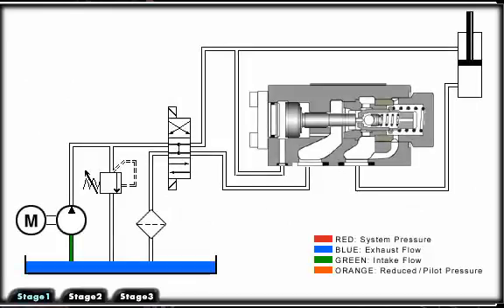Because of slight spool leakage on standard directional control valves, we must add a check valve to the circuit if we need to hydraulically lock a cylinder. This type of check valve is referred to as a pilot operated check valve.